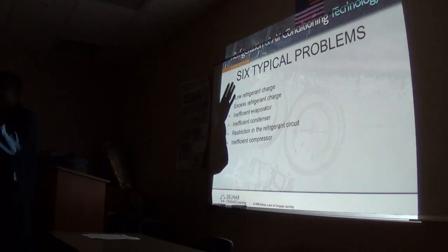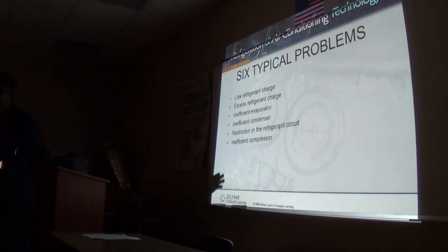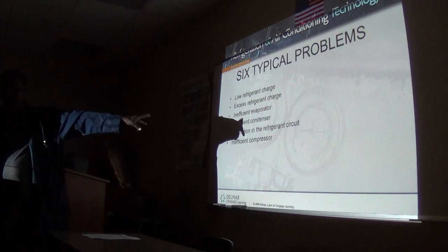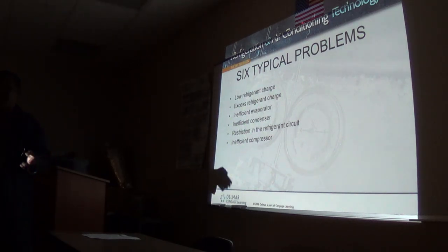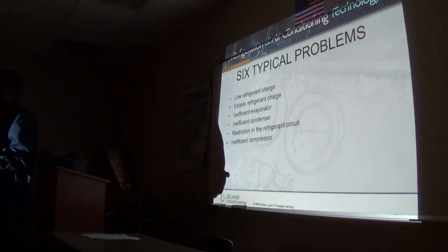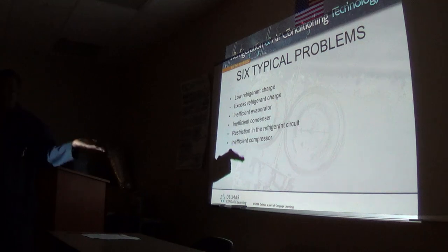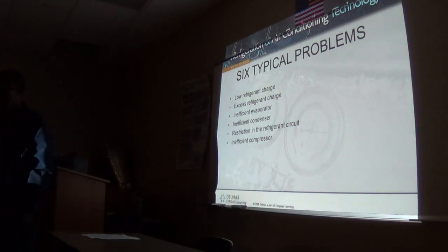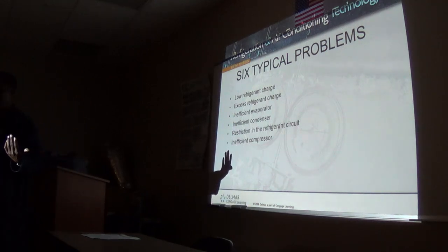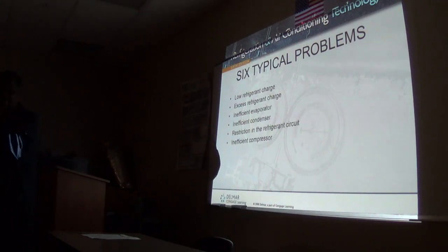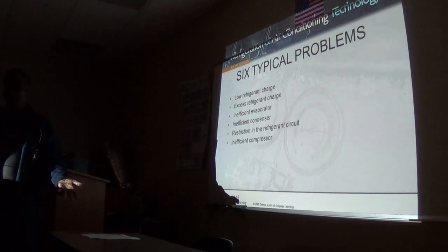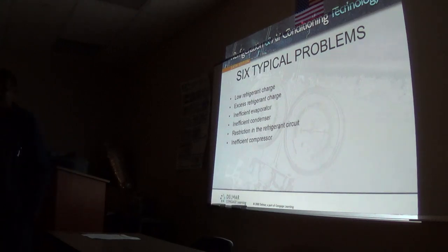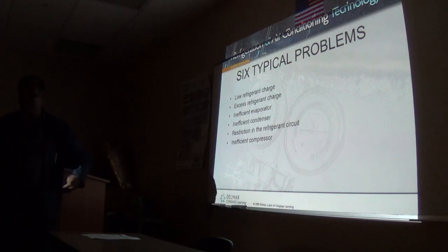But that's the one place. With all these domestic refrigerators, when you have that problem with restriction, that's it. That's where you block. And religiously, with almost every 134A system with a cap tube metering device, that happens. I've changed so many of them, I had to repair so many because of blockage. Not the compressors, the compressors are strong. They work, they're like workhorses. Just the blockage you have to take care of.